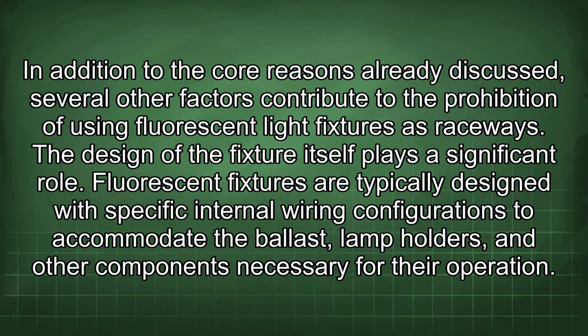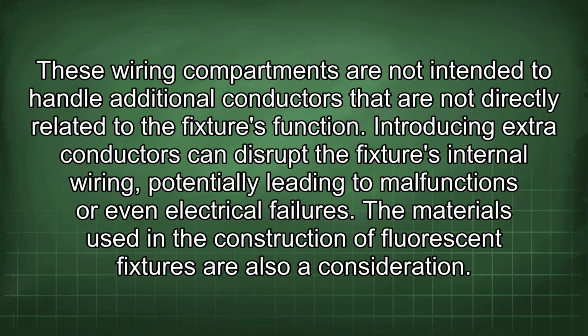Fluorescent fixtures are typically designed with specific internal wiring configurations to accommodate the ballast, lamp holders, and other components necessary for their operation. These wiring compartments are not intended to handle additional conductors that are not directly related to the fixture's function. Introducing extra conductors can disrupt the fixture's internal wiring, potentially leading to malfunctions or even electrical failures.